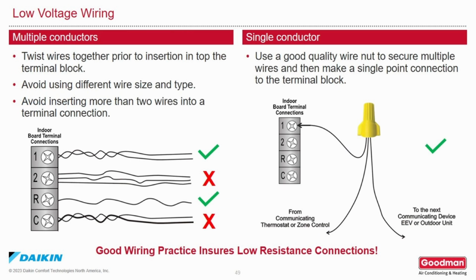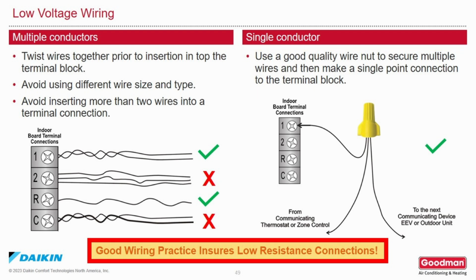When you're dealing with multiple conductors, twist the wires together before you insert them into the terminal block. Avoid using different size wires and different types. Also avoid inserting more than 2 wires into the same terminal connection. On the communication daisy chain, you can use a single wire connected to the terminal board and a good quality wire nut off the circuit board to complete the daisy chain. Remember, good wiring practices ensure low resistance connections for a cleaner communication circuit.